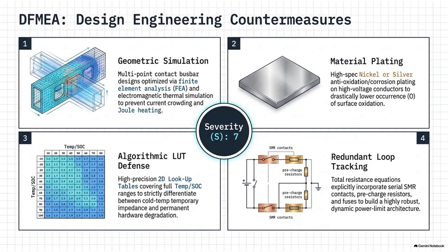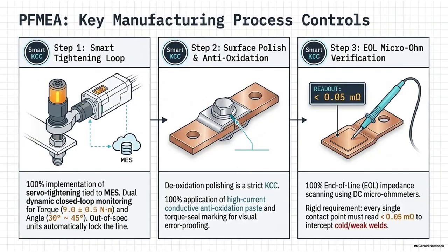That is wild. But even with perfectly engineered, squishy microbumps, you still have the issue of oxidation over time if the bolt relaxes even a fraction of a micron, right? You get that copper oxide crust. Which leads to the material specification countermeasures. Bare copper is completely unacceptable in these critical high-voltage joints due to the insulating properties of copper oxide. The DFMEA mandates high-specification plating, specifically nickel or silver plating, over the copper bus bars. Silver plating, I mean, silver is incredibly expensive for mass production. Why is it justified here?